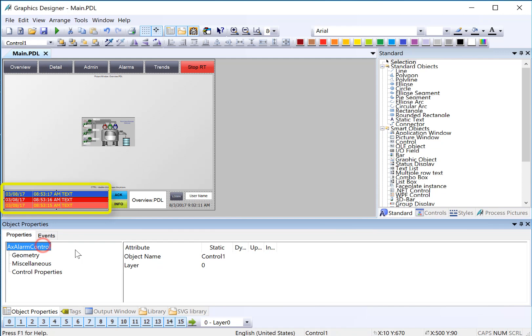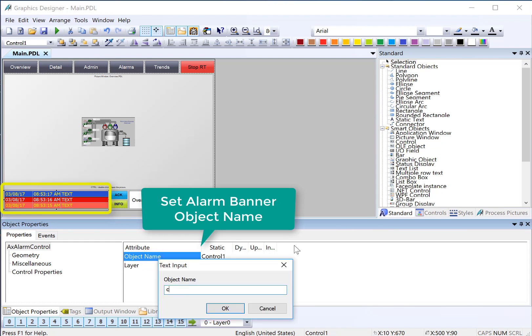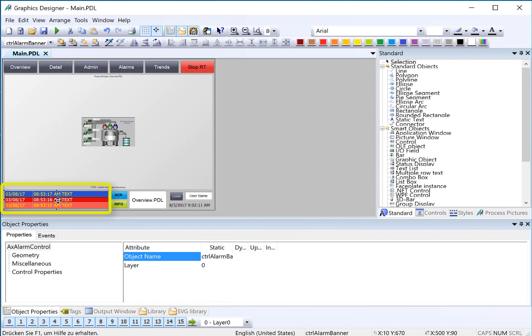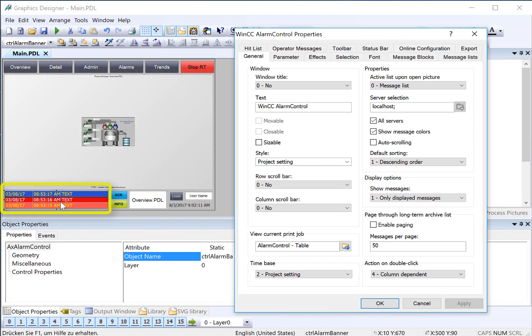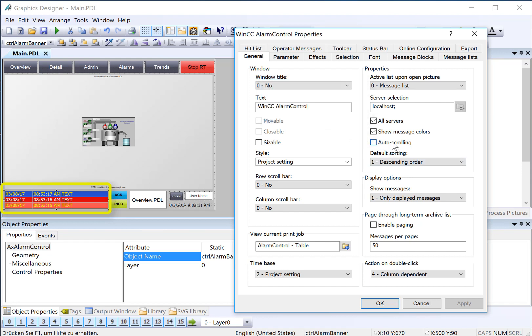We're going to go to our alarm control and change the name so we can pick it out of a list, because we have more than one control on this page. I'm going to call this Alarm Banner. Next, let's take a look at the properties. If we want to acknowledge an alarm that's on this banner, we have to select an alarm and then hit Acknowledge. We have to duplicate the single acknowledgement functionality on the toolbar. The first thing to do is make sure that auto-scrolling is unchecked. That allows you to make selections of individual alarms on the control.